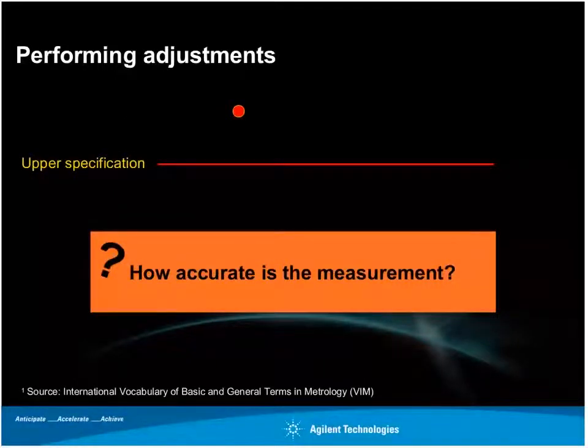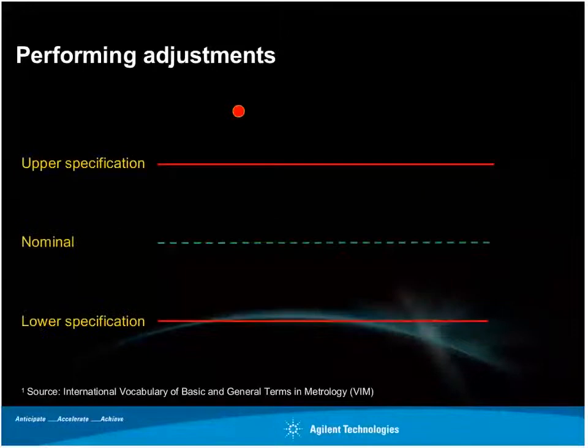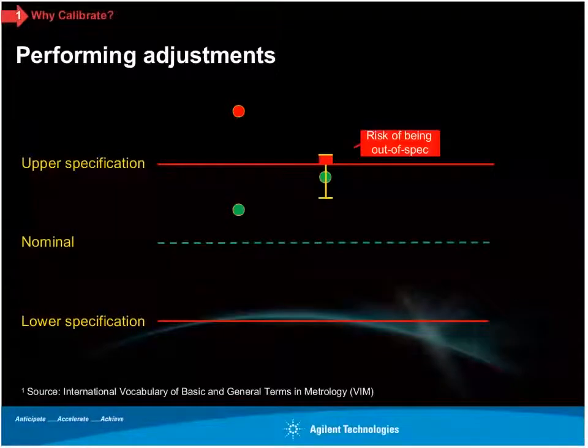And just on a diagram, I wanted to repeat this one particular one. If you have a 2-sided specification and you're way out of spec, then everyone knows that's a fail. And if you're way inside, everyone knows that's a pass. The question is always, if you're just inside the specification or just outside, what do you do? And that is where this statistical concept of measurement uncertainty comes about. And in particular, if there's a portion of that that's outside the spec, that represents your real risk of being out of spec.